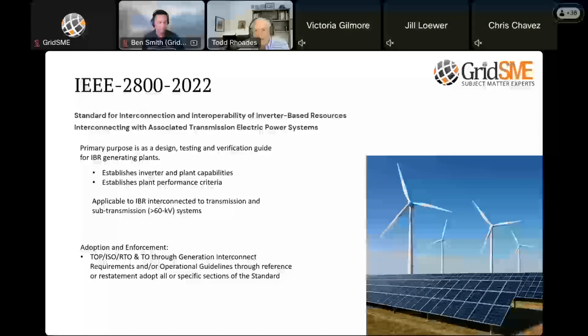It's applicable, utilizing NERC terminology, to both Category 1 and Category 2 IBR plants. Specifically, it does not limit to an MVA, but it is strictly connected to transmission and sub-transmission — so anything over a 60 kV system.